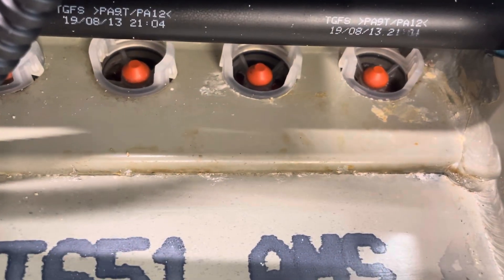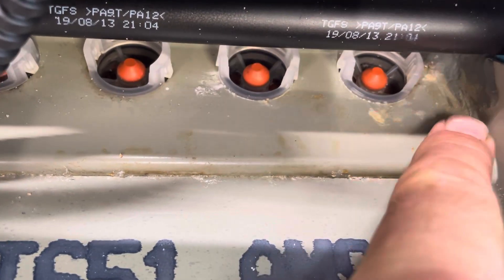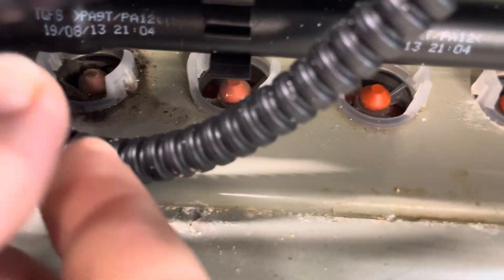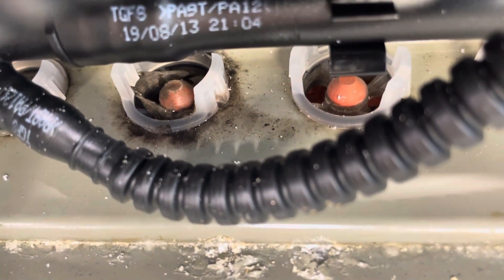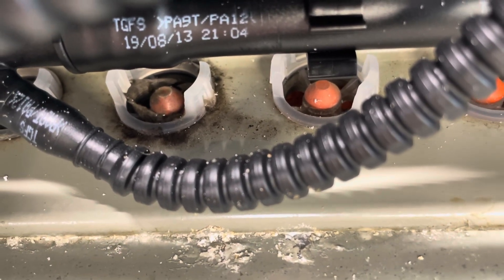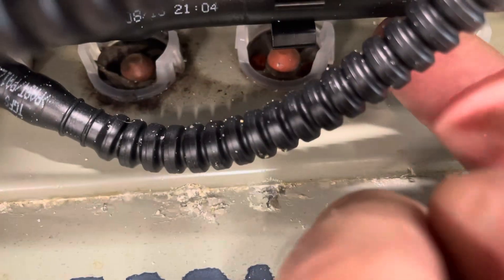Over here these valves look pretty good, but you can see what appears to be some signs of water intrusion — a little corrosion around here and around here as well. Looking further down, we definitely see some dirt around it, and it looks like there's a little bit of something in there — something organic, maybe a piece of a maple seed or some grass or some sort of gunk in there. This one over here as well looks a little dirty.